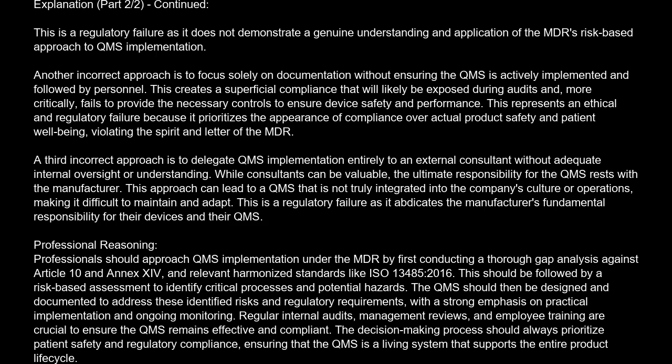Professional reasoning. Professionals should approach QMS implementation under the MDR by first conducting a thorough gap analysis against Article 10 and Annex XIV, and relevant harmonized standards like ISO 13485:2016. This should be followed by a risk-based assessment to identify critical processes and potential hazards.